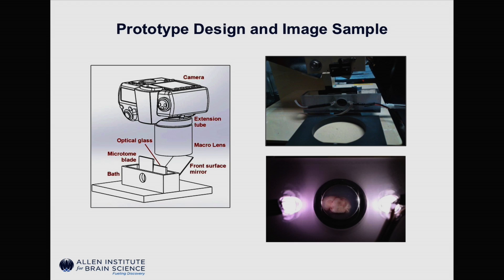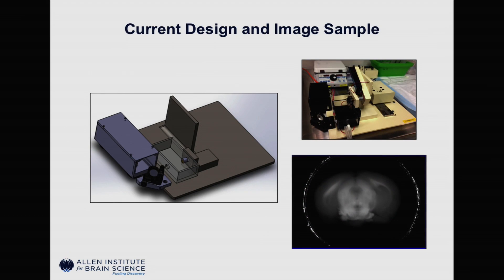Using this feedback, the engineering team came up with what we're using as our current design. One of the biggest changes was that it was determined we didn't need to use a color image — we could use a black and white camera. The only change we had to make was that we darkened our agarose to provide contrast between the tissue and the embedding material. It took up a slightly smaller footprint, so it was a little bit easier to use. Elliot will go over the design of this hardware and the software used to actually acquire the images.